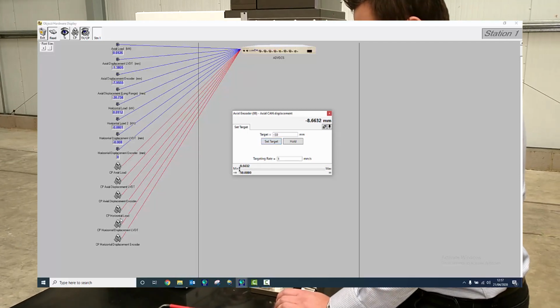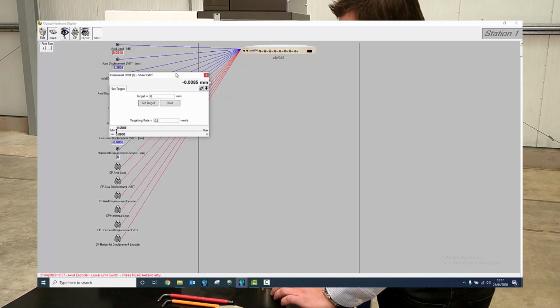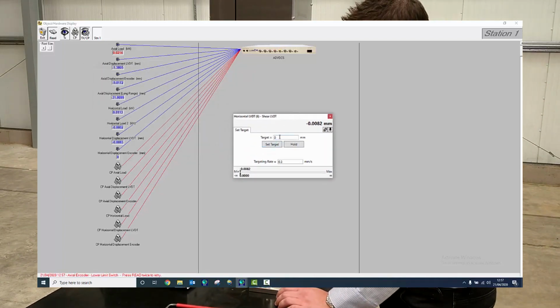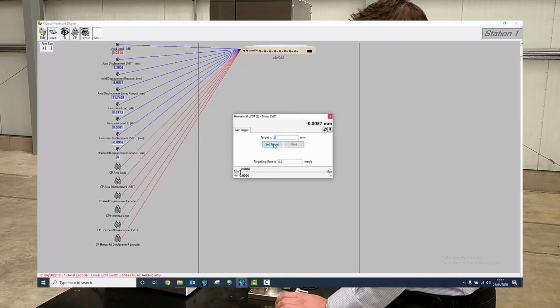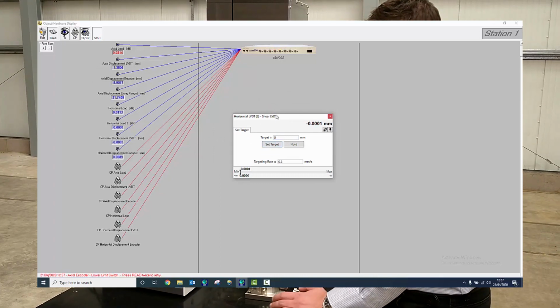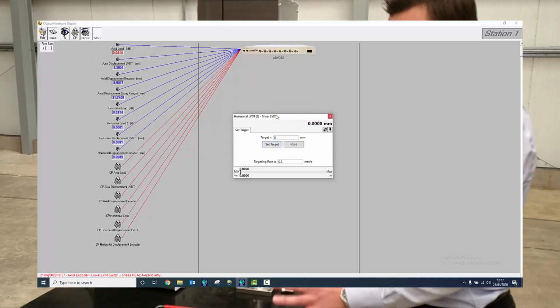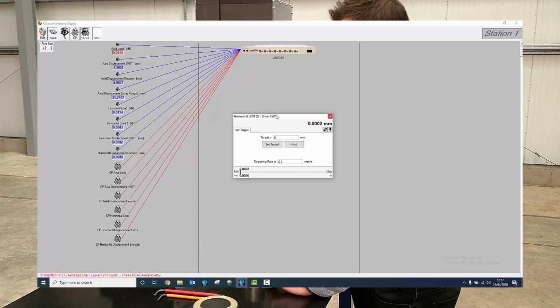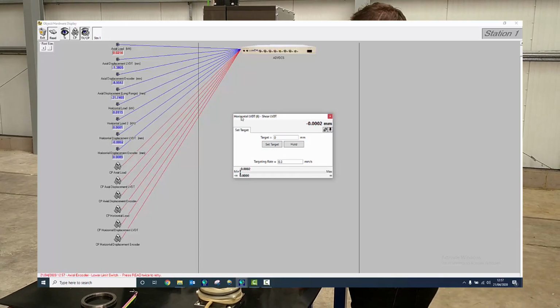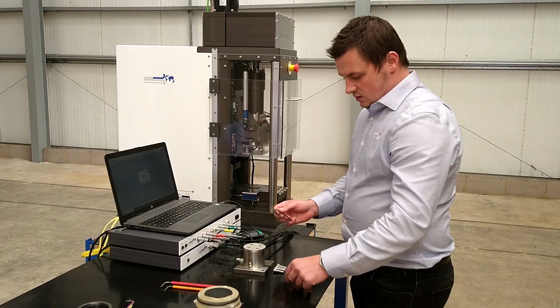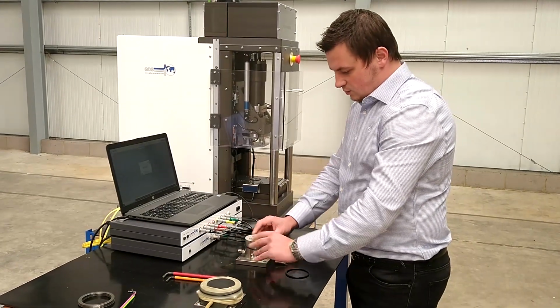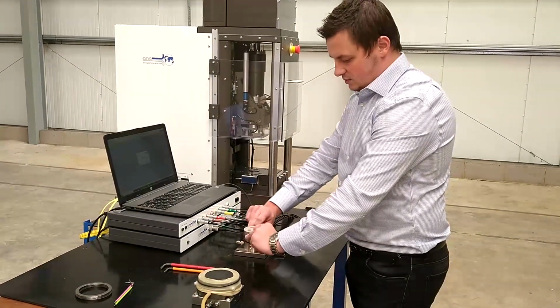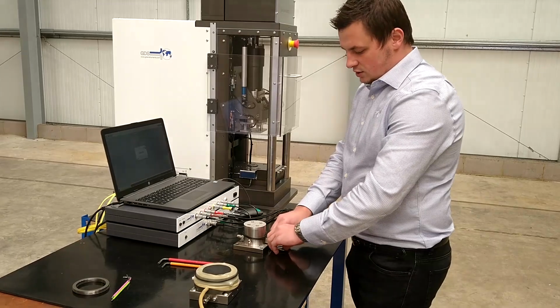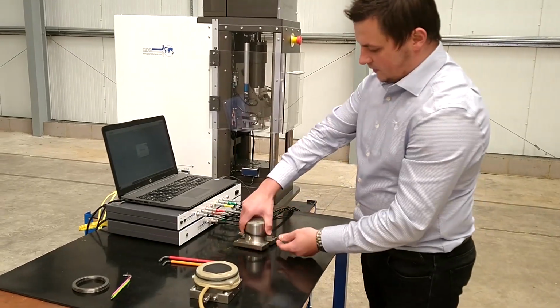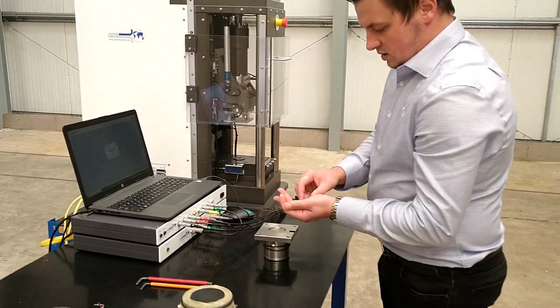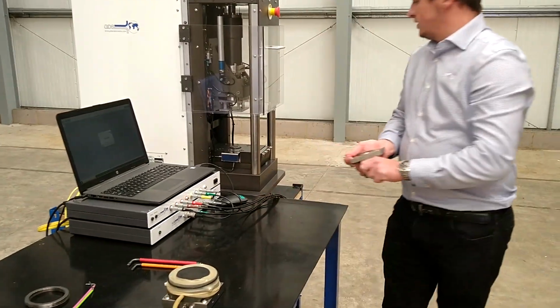We also need to check, as we did in the previous step, that we are targeting the 0 position on the shear LVDT, because that is the position in which the top cap and the pedestal will be aligned for the test. So our machine is fully up, so we can first place the top cap. I'll put the O-rings on the top caps that we'll then later use to clamp the membrane and place our top cap inside of the machine.